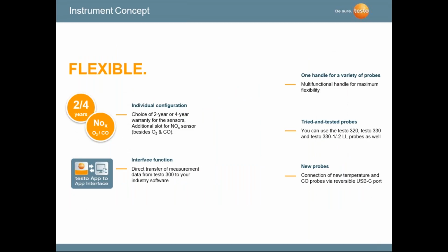Again, it has the capability of using two sensors, oxygen and carbon monoxide, and we're using an oxygen carbon monoxide. This is really used a lot for boiler tuning. Oxygen and CO, temperature is standard, pressures are standard with Testo. When you get to a 2-gas instrument, this is used a lot for boiler tuning. We also have the capability of measuring NOx, which is the 3rd sensor, and the 3rd sensor allows us to measure not only for safety, but also for environmental measurements like NO and NOx.